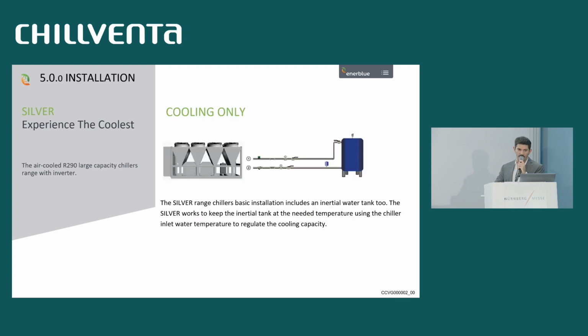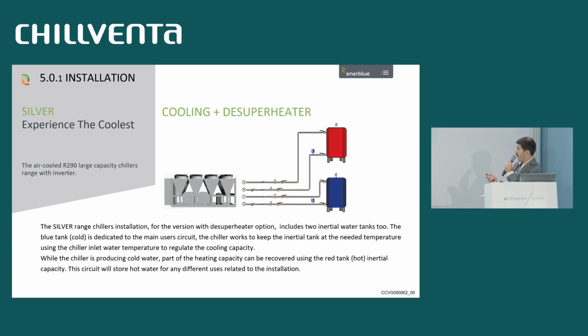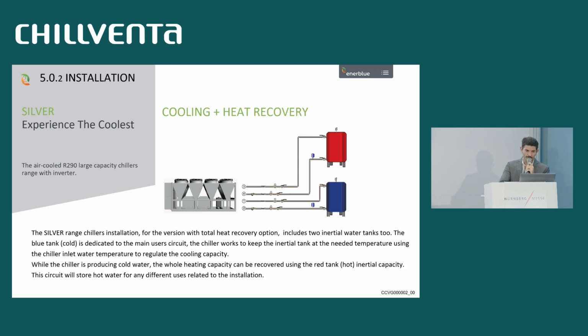It will be possible to provide the unit in a cooling-only version, so the 2-pipe traditional version, providing cool water to a correctly dimensioned water tank, or, if there is a proper amount of water in the water circuit, also without a water tank, but let's consider this the standard case. There is also a version with a desuperheater, with an additional plate heat exchanger to partially recover the heat of the cooling capacity, supplying a hot water tank. And in some cases, extremely interesting, the total heat recovery version. So we cool down a cold water tank, and at the same time we recover the same energy to heat up a second water tank.